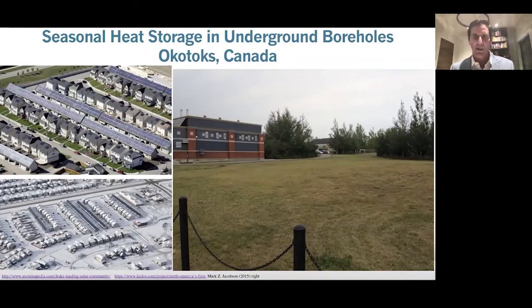While batteries cost on the order of $200 to $300 per kilowatt hour of electricity storage, the storage portion of this costs less than $1 per kilowatt hour for heat storage, but it's thermal, not electricity. So it's actually inexpensive to run and very reliable, even though the efficiency isn't great. It's only about 58% round trip efficiency from the sun coming in the summer to the heat coming back in the winter, which is much less than batteries. But it's so cheap, you can afford to waste some energy there.